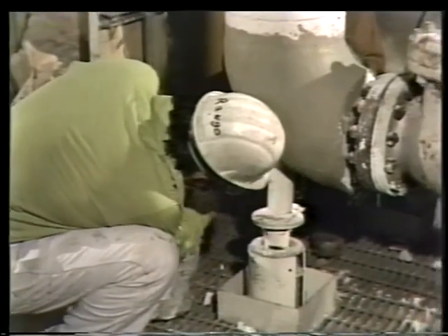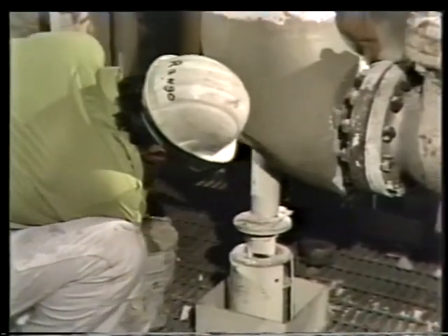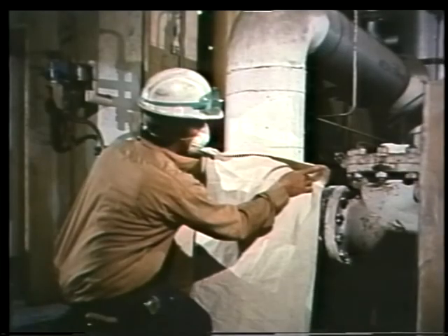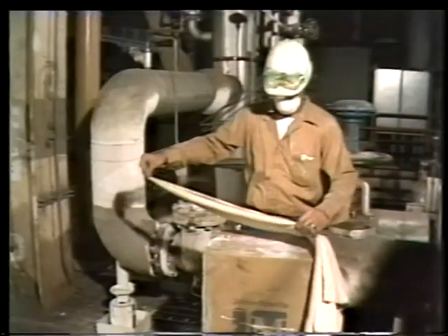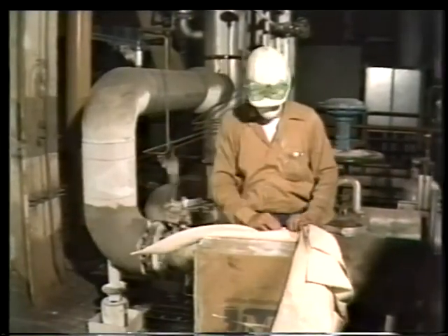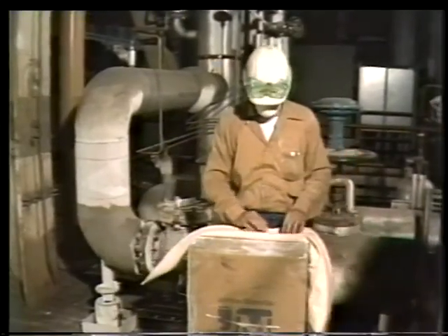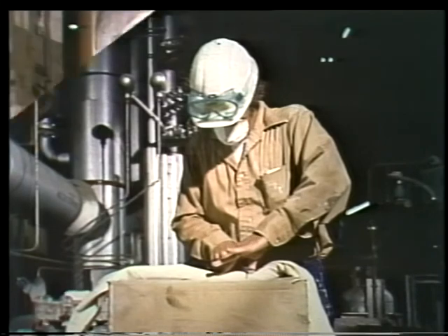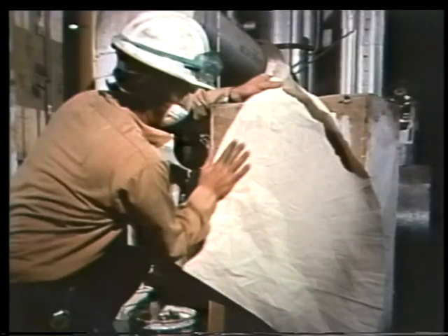Before the elbow can be lagged, the lagging cloth must be cut to the correct size and shape. The worker measures the lagging cloth by laying it out against the elbow. Then the cloth is folded into a triangle and doubled over 3 times. The lagging is cut to the correct length with a sharp knife. When the cloth is unfolded, it forms a quarter circle, just the right shape to stretch over half of the elbow.